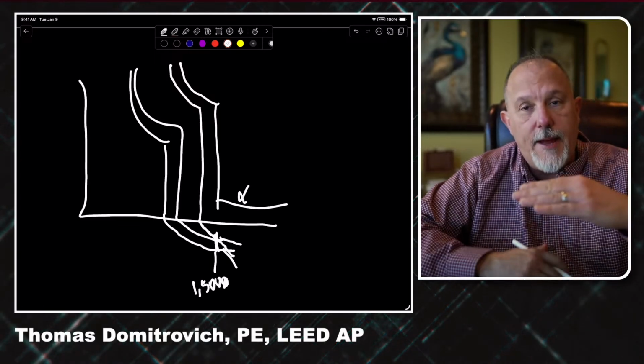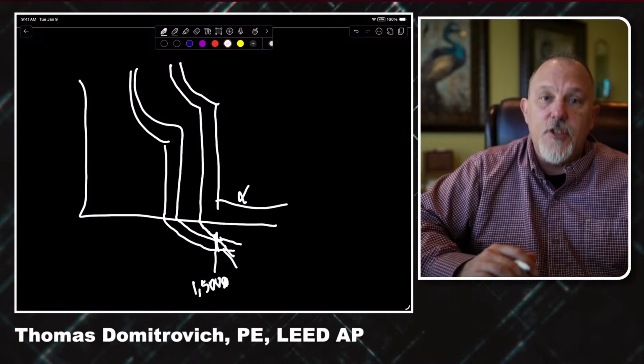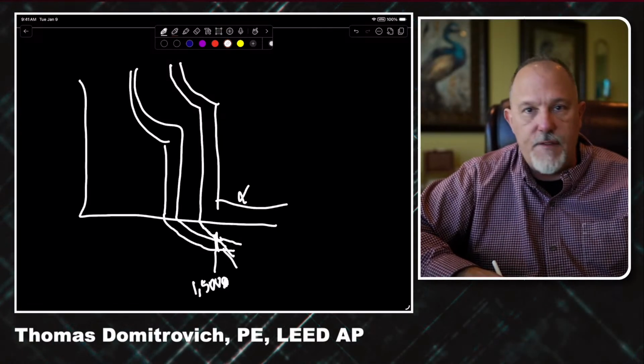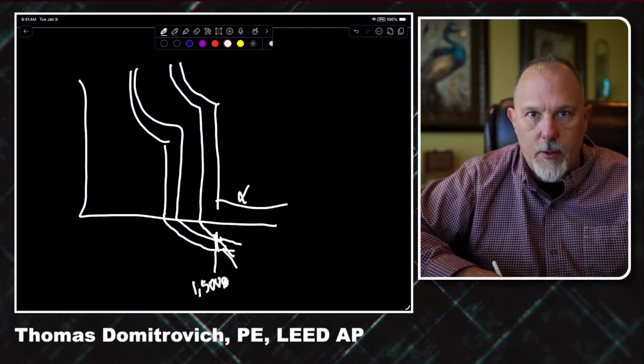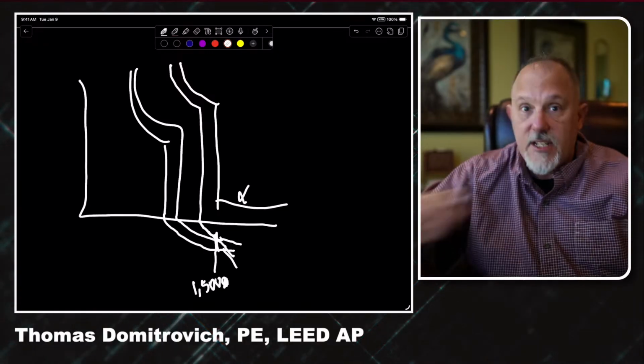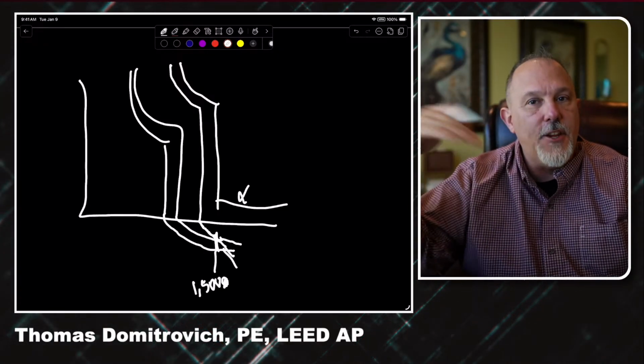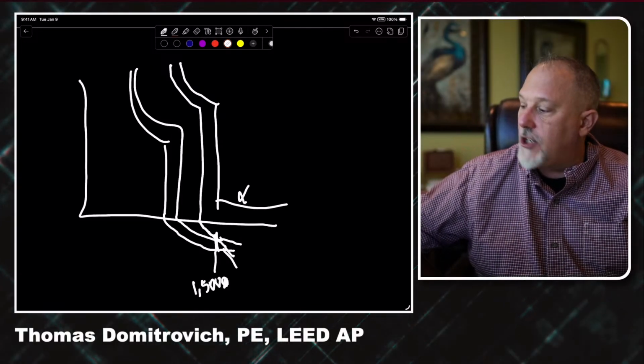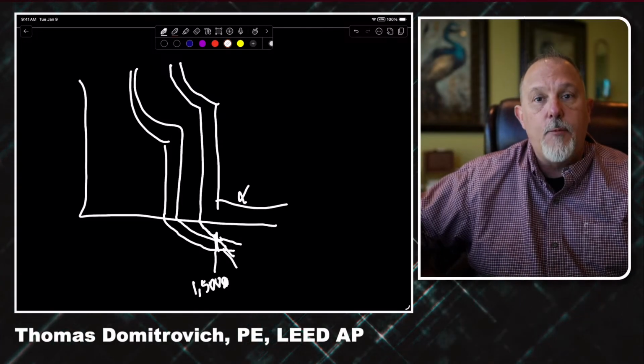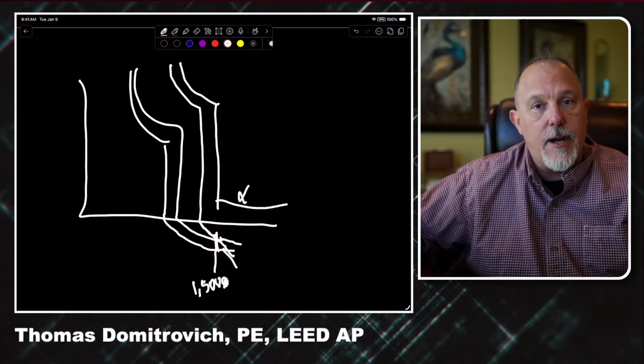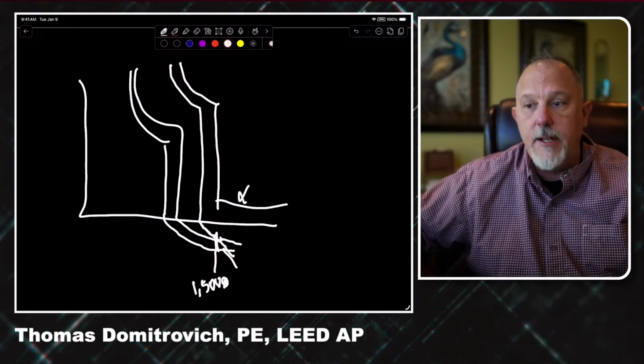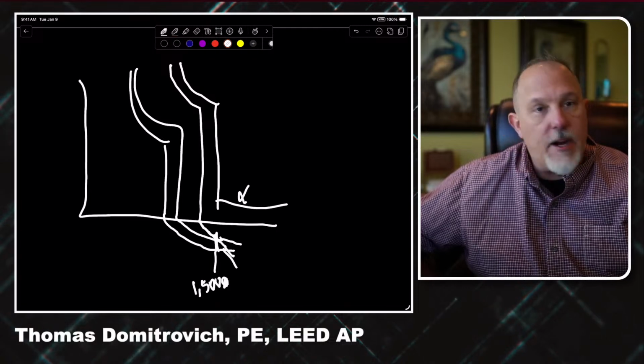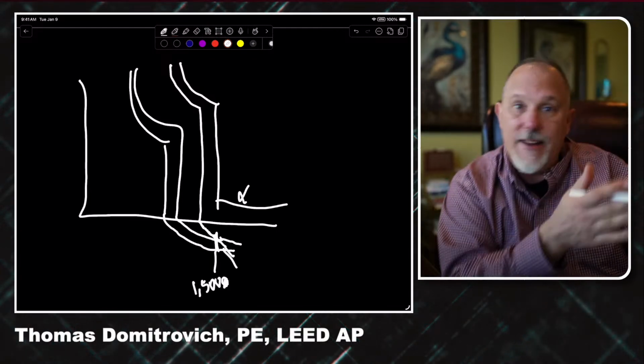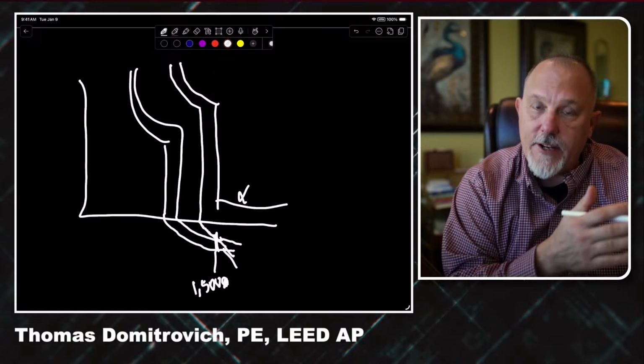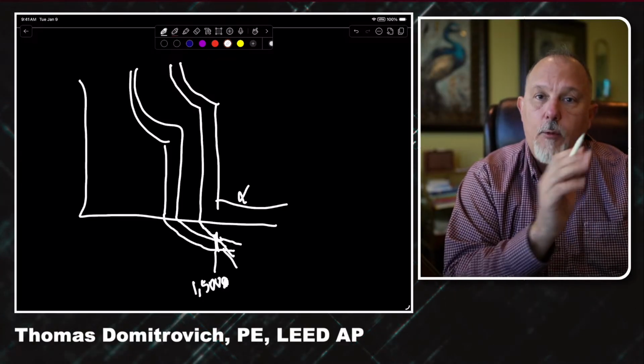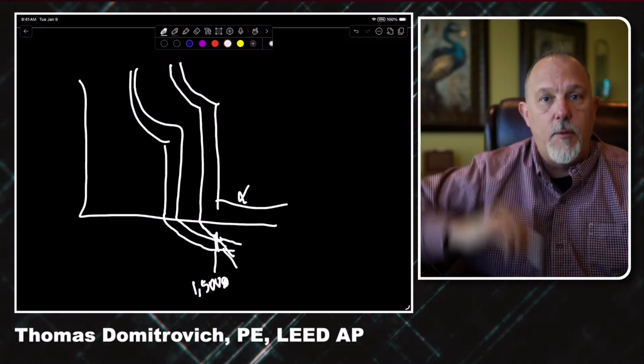So below that 0.1 seconds, manufacturers probably have that data, but we just cut it off because it gets pointless at that point. But it's important for selectivity. To get you to that lower number, we shot these in a lab, and we used the series ratings configuration in UL 489, and we know where that crossing point is, and we plotted it in that table. So manufacturers are telling you the current value beyond which they will both open.